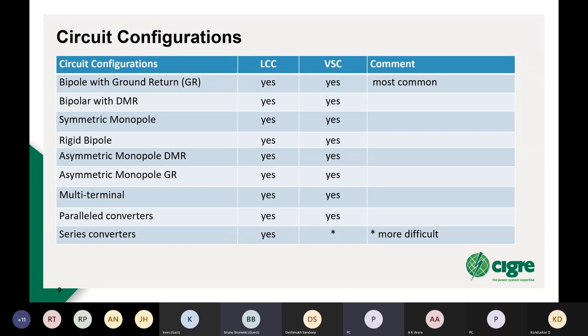Multi-terminal configurations are possible with either technology. There are examples of systems with multi-terminal in the world in both technologies. Parallel converters are, of course, common in both technologies, and very useful for increasing the rating of the system beyond the rating of a single switching device, a thyristor or IGBT. And of course, series converters are possible in both technologies as well.